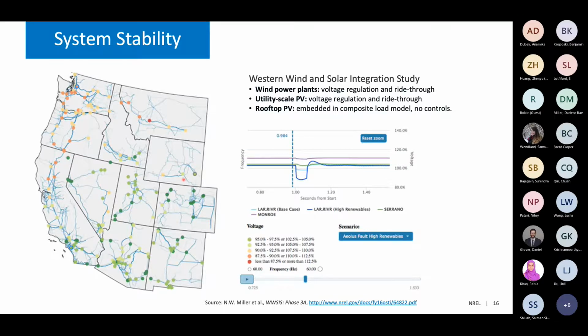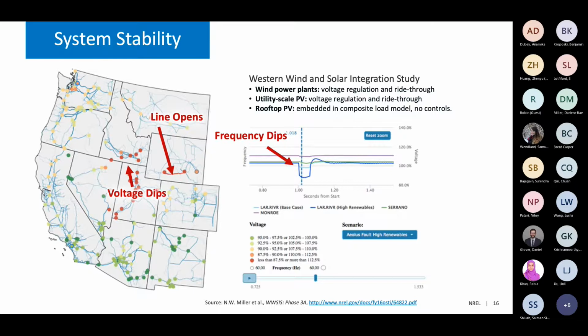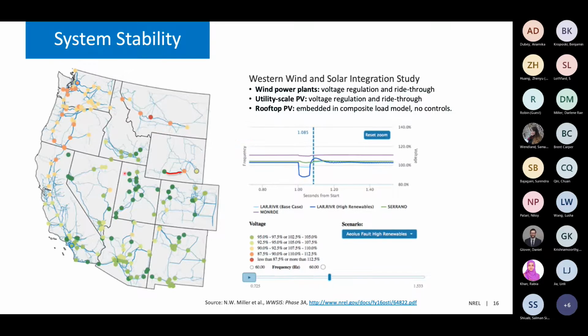We open this line, which causes a voltage dip in the middle of the Western US and also a frequency dip. But these plants are set up to respond very quickly, pulling the rest of the system back into synchronization and recovering that frequency. As you can see, even though this line opens up, the power starts to reroute, and we're able to eventually stabilize back around 60 hertz.